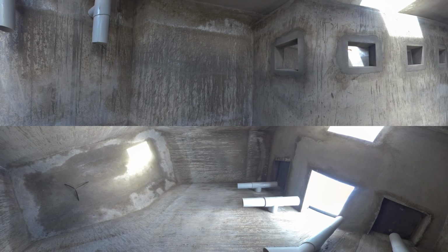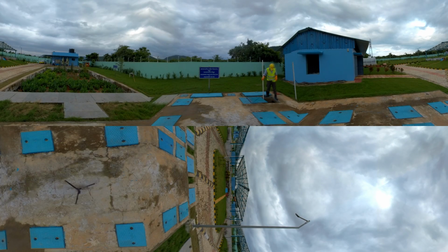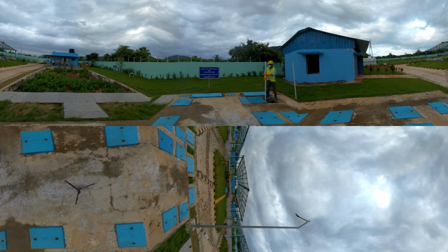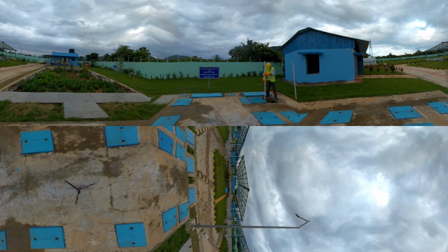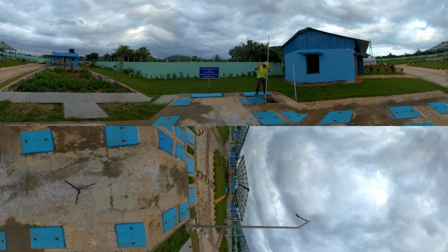The third operation is to check the sludge level every 6 months. To do this, you have to take a clean long stick, wrap a white cloth around it and insert it into the inlet of the settler chamber till it touches the base. Take out the stick and measure the level of the sludge mark on the cloth. If it is higher than 50 cm, then desludging must be carried out.